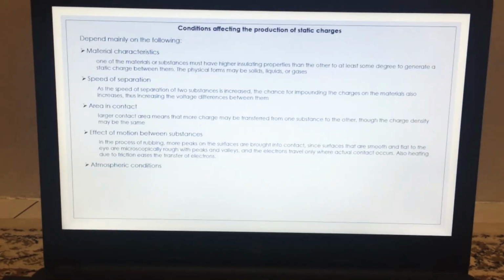Conditions affecting the production of static charges depend mainly on the following. Firstly is the material characteristic. One of the materials or substances must have higher insulating properties than the other to at least some degree to generate a static charge between them. The physical form may be solid, liquids or gases. The second one is the speed of separation. As the speed of separation of two substances is increased, the chance for impounding the charges on the material also increases, thus increasing the voltage difference between them.